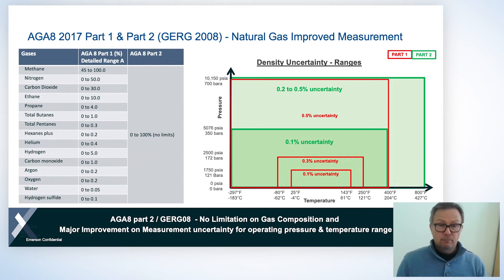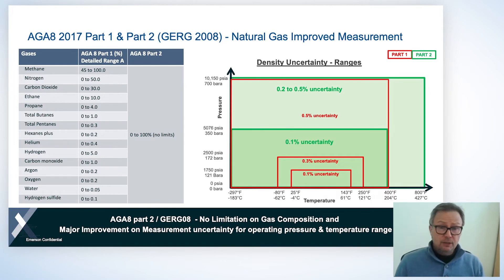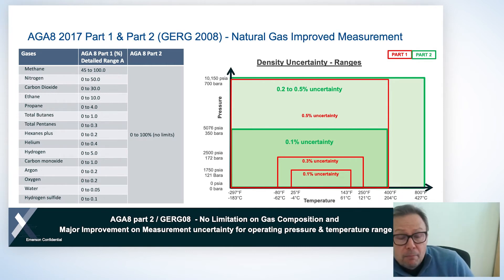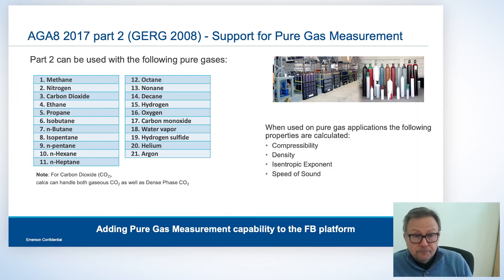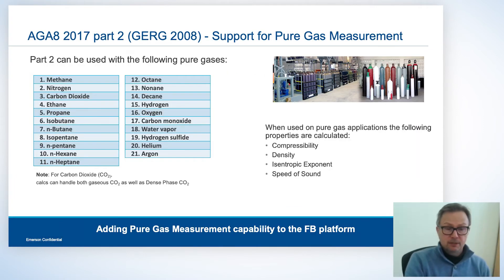So very good measurement uncertainty over a significantly wider pressure and temperature range and a significantly wider gas composition range. And remember, if we go outside of that operating envelope with AGA8 part two, we still get something between 0.2 and 0.5% measurement uncertainty.